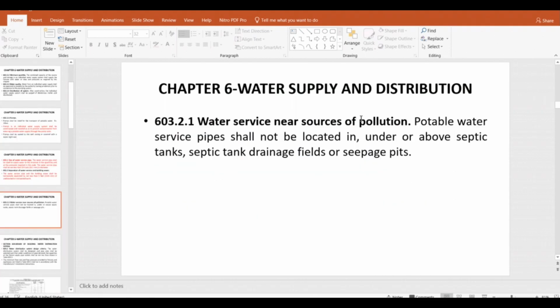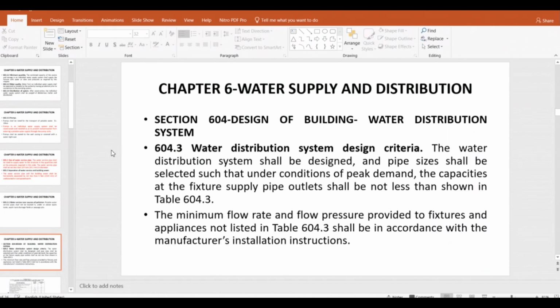Water service near sources of pollution. For example, you have to make sure that your water supply pipe, wherever your pipeline is passing or your water supply tank is, is not passing very near to the septic tank or holding tank or any sewerage tank. So it should not pass over the septic tank, below the septic tank, or to the left or right side of it. It should not pass very near to the septic tank or holding tank. So we have to make sure of this when we make the routing for the water supply piping.